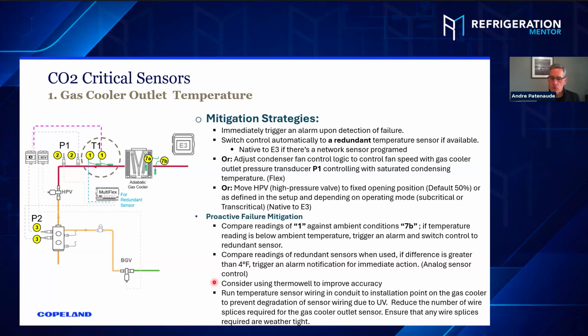I was at an OEM last week, and their sample unit that they were showing me was using thermowells, because now you don't have to worry about that whole insulation, but it's a costlier thing to do. When I was out in Quebec, I was at a few Arneg sites, and that's what they had on their Ref Plus gas coolers, thermowells. Goodyear also has thermowells in some of their legs. So, yeah, I've seen those.